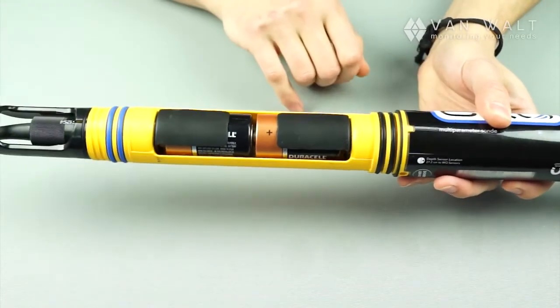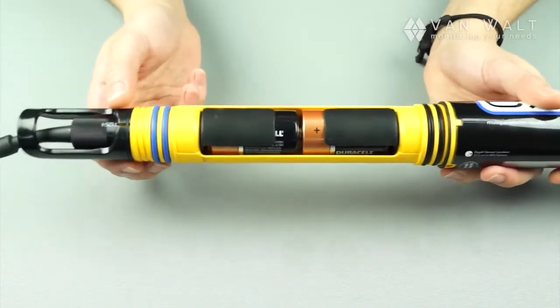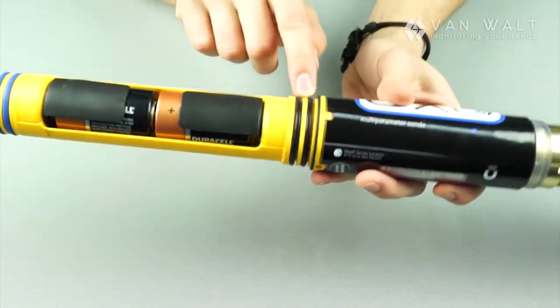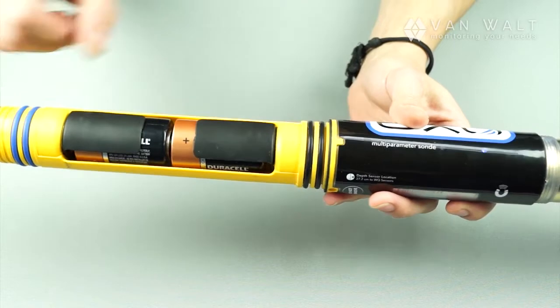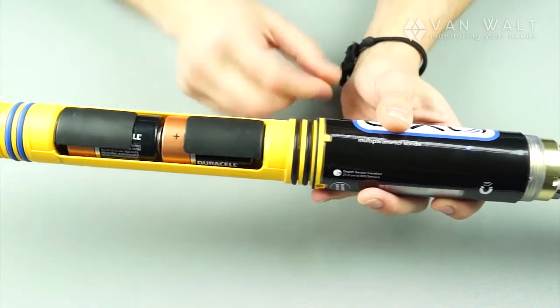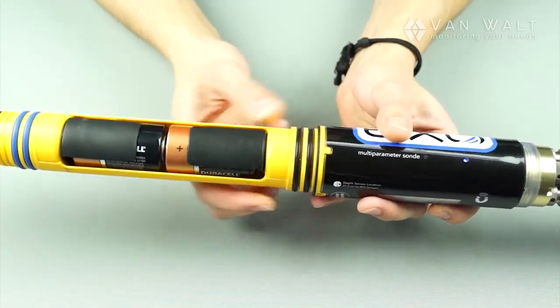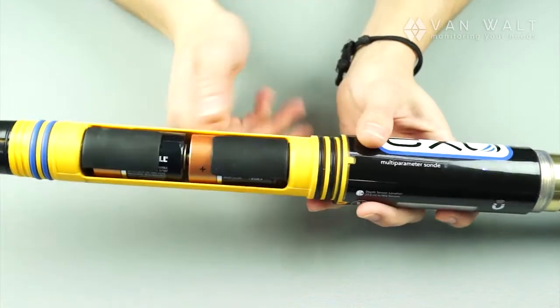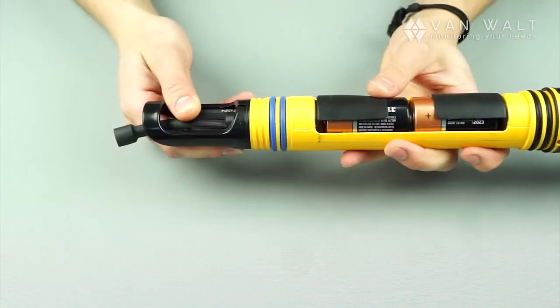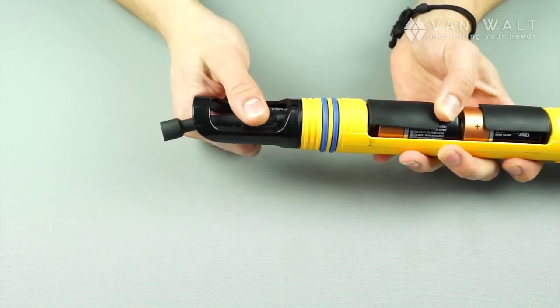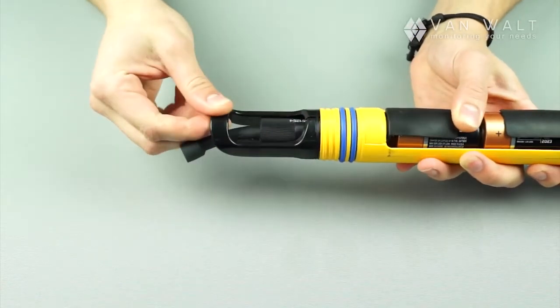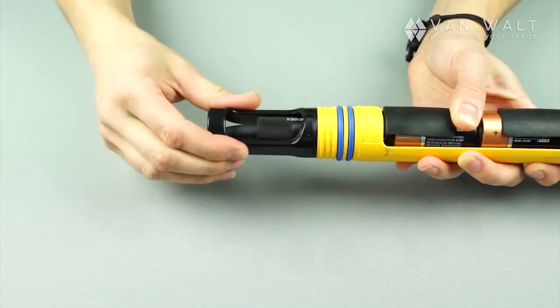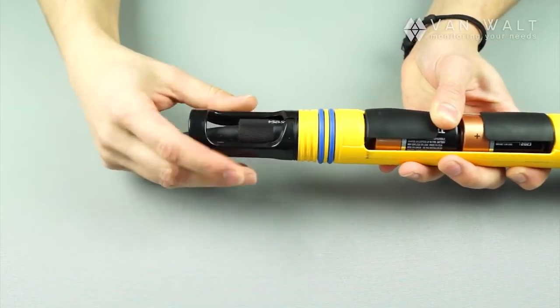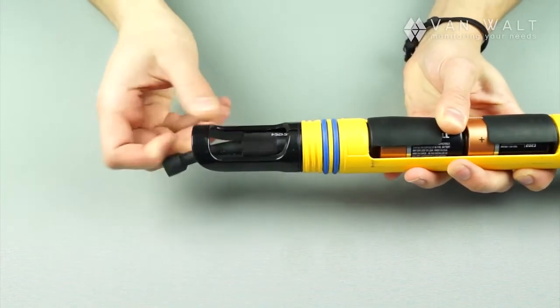Keeping everything watertight in here, once we've changed our batteries, there are four O-rings, 2 here and 2 on the back. It's important that we keep these clean and slightly lubricated when we replace the cover to stop moisture ingress. So the last part of the device is the suspension hook. This can be easily changed with this O-ring. Once our cover is on, this is pretty robust.